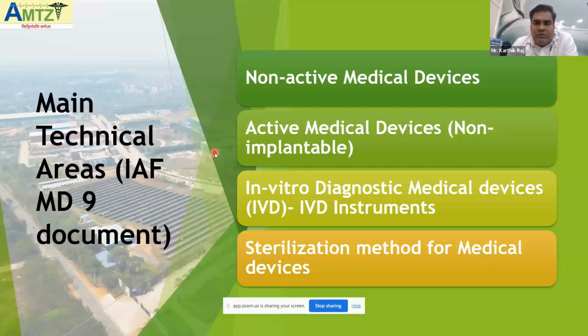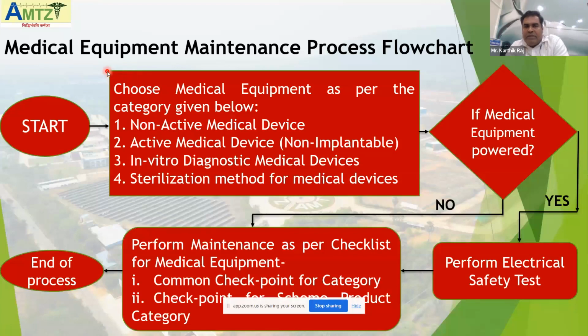Now, how does the scheme proceed? Take a hospital as an example. In a 100-bed hospital, you will have more than 1,000 pieces of equipment. When I talk about equipment, it can be a surgical knife, a BP apparatus, a sphygmomanometer. All of these are biomedical equipment, that is, medical devices. Now you have to map these 1,000 pieces of equipment to one of these four categories, or to the categories that are not applicable, which I mentioned in the previous slide. That is the first step. The medical equipment maintenance process for the scheme starts with choosing where your equipment falls: the first category, non-active medical device; the second, active medical device, non-implantable; then IVD instruments; and the fourth, sterilization method for medical devices.